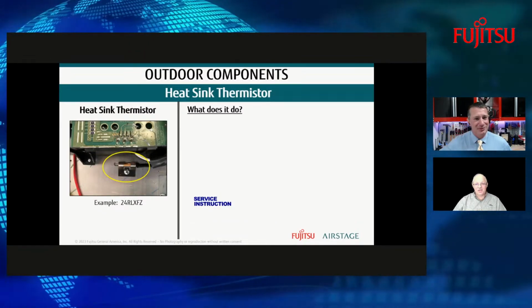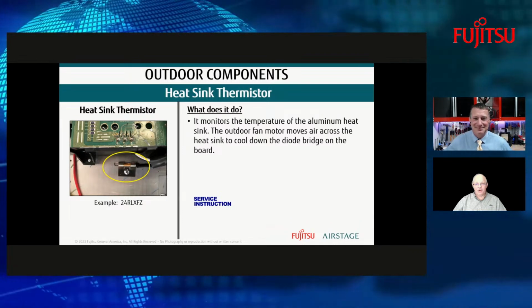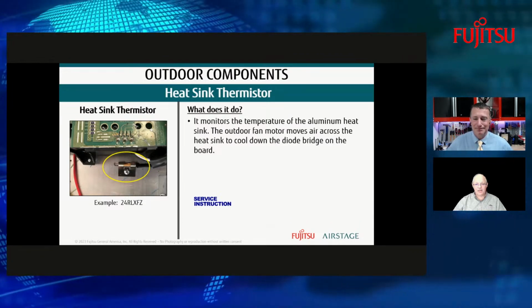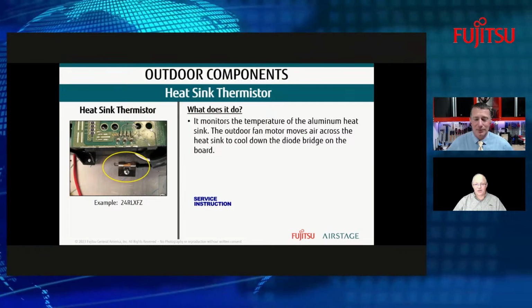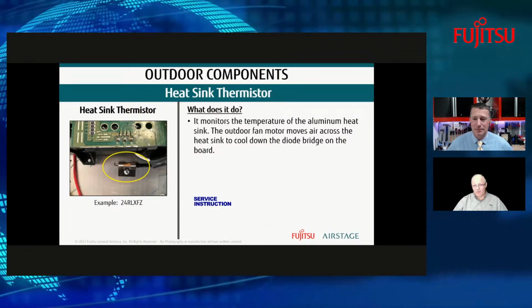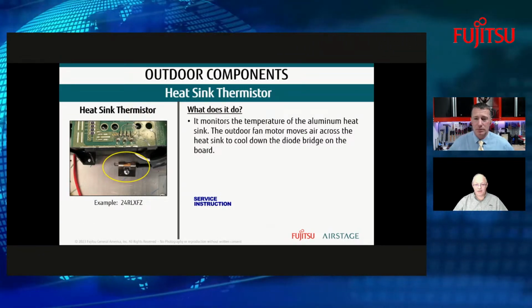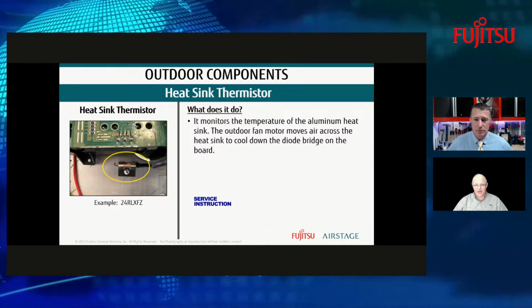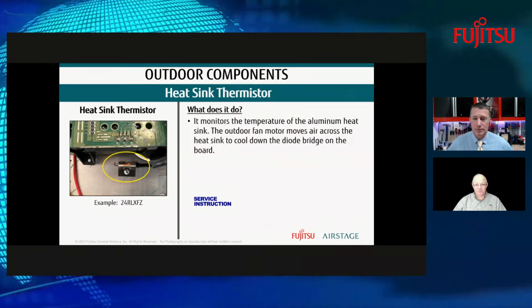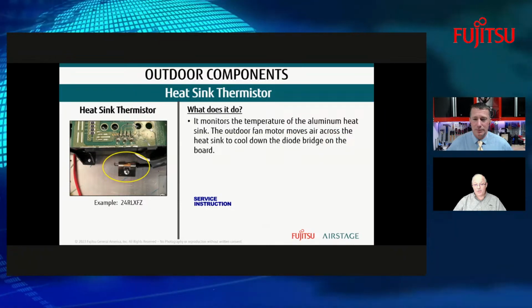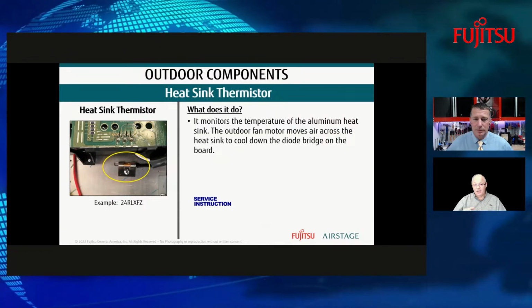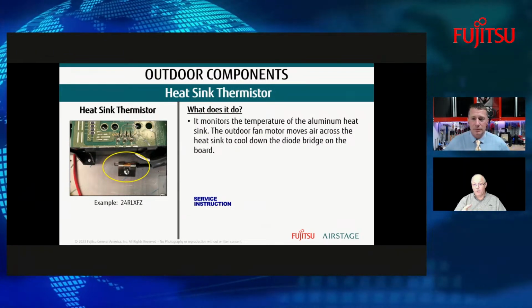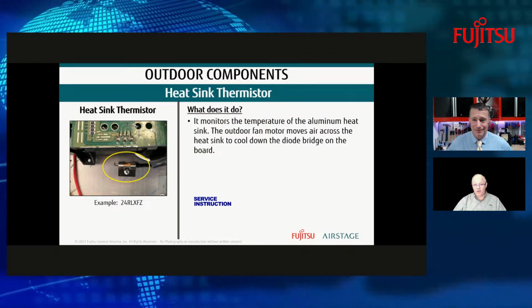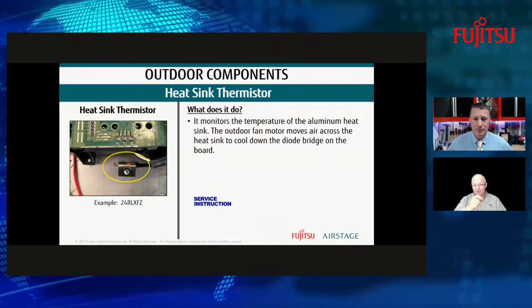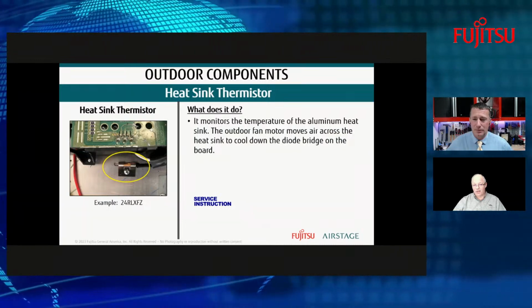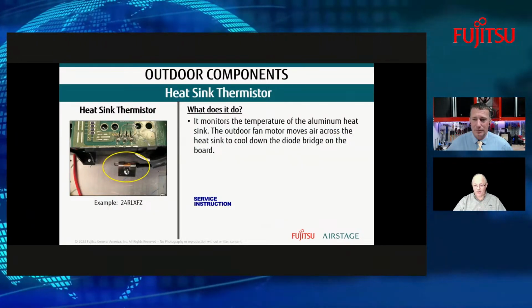We got another one. So what's this one do? Well, it's monitoring the temperature of that aluminum heat sink that it's tied to. So, if the outdoor fan motor continues to move air across that heat sink, then the diode bridge is going to be happy. If not, then this thermistor is designed to open up before you lose your diode bridge, because that thermistor is a whole lot less expensive than that board.